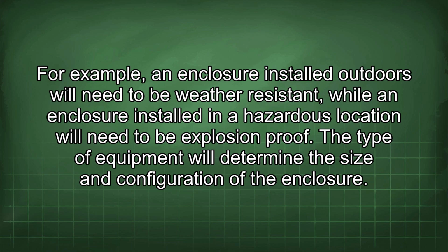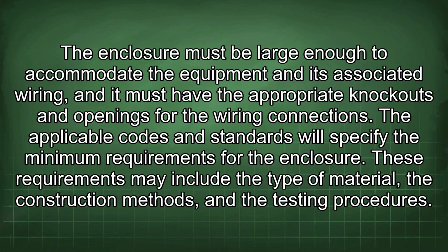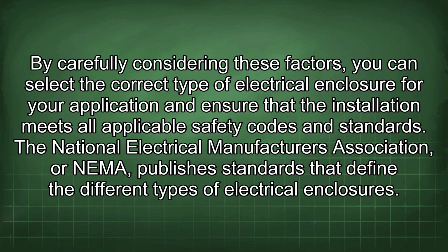The type of equipment will determine the size and configuration of the enclosure. The enclosure must be large enough to accommodate the equipment and its associated wiring, and it must have the appropriate knockouts and openings for the wiring connections. The applicable codes and standards will specify the minimum requirements for the enclosure. These requirements may include the type of material, the construction methods, and the testing procedures. By carefully considering these factors, you can select the correct type of electrical enclosure for your application and ensure that the installation meets all applicable safety codes and standards.